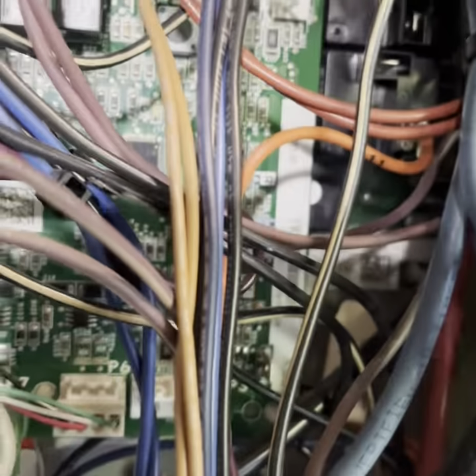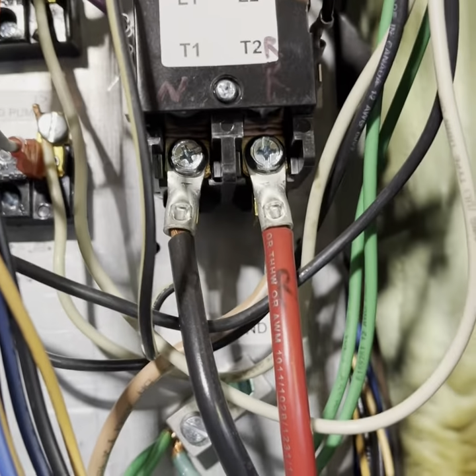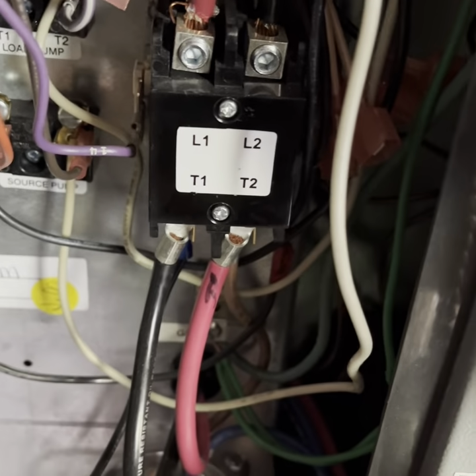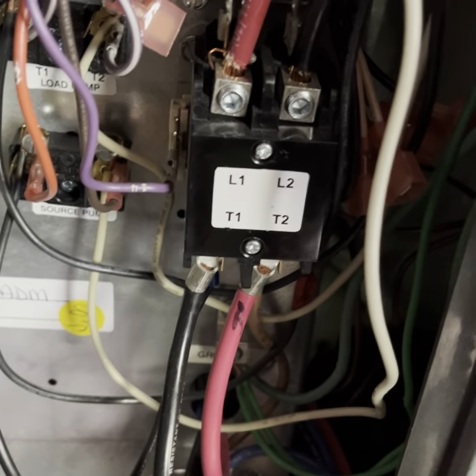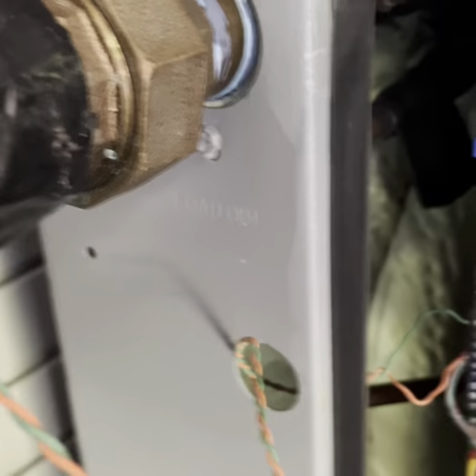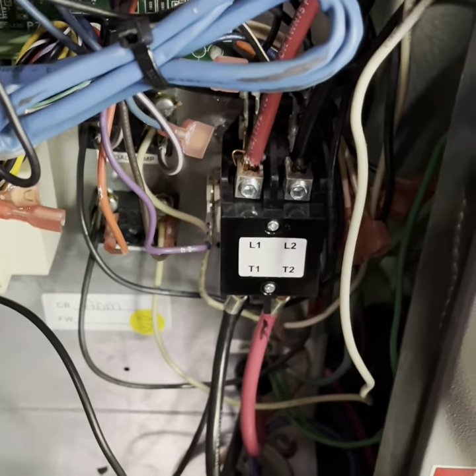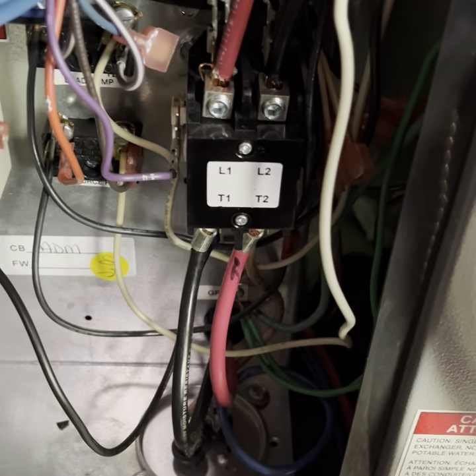All right, made the changes, let me show you what I did. We just moved those onto that contact, and I actually dropped it down to the bottom of this contactor here, because there's no flow proving switch on the load end, so it's not going to stall out or fault out trying to get those pumps running before the contactor comes in.